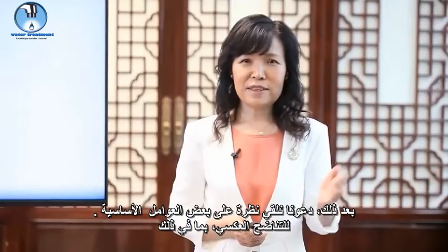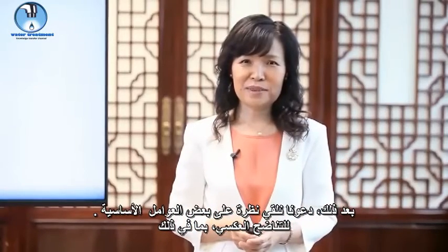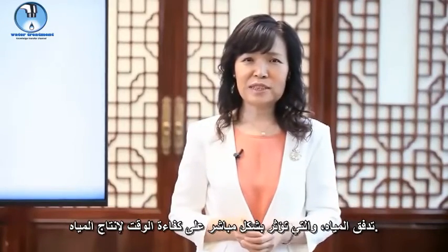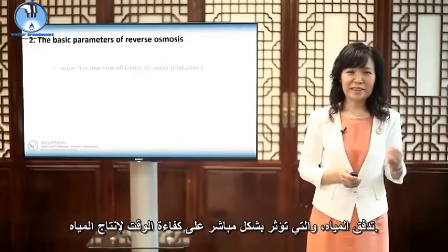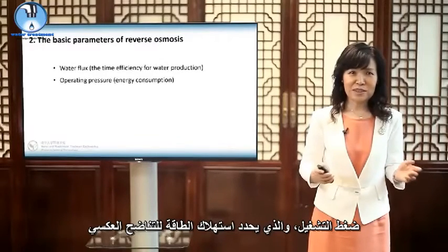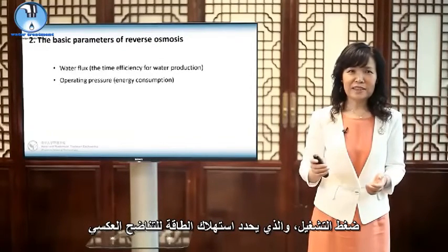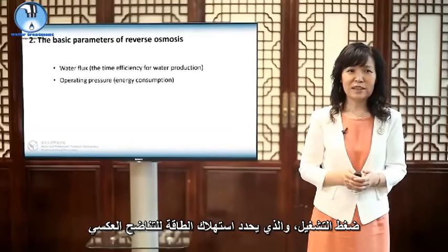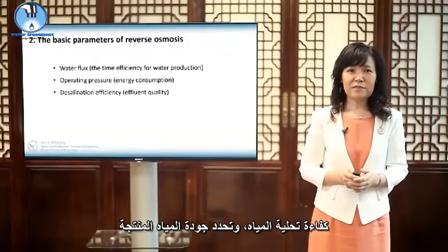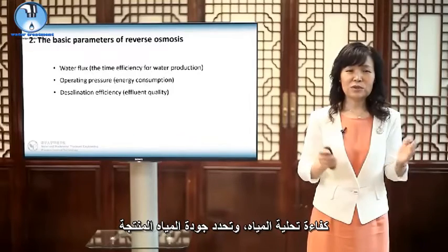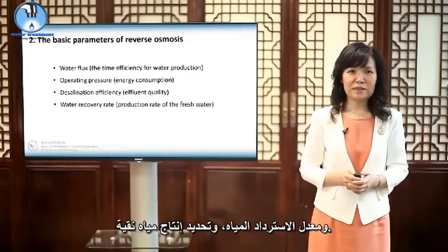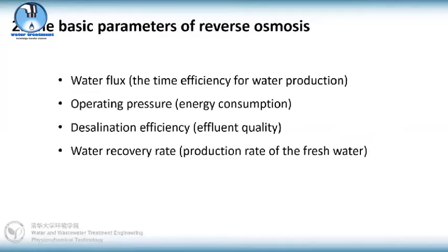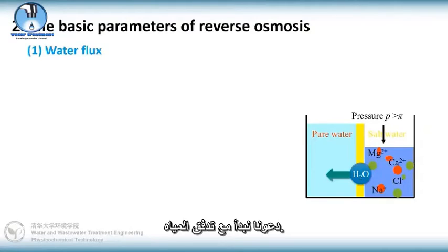Next, let's look at some basic parameters of reverse osmosis, including water flux, which directly influences the time efficiency for water production, operating pressure, which determines the energy consumption of reverse osmosis, desalination efficiency determining the effluent quality, and water recovery rate determining the pure water production. Let's begin with the water flux.